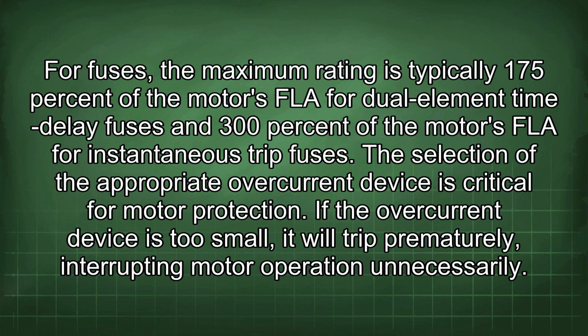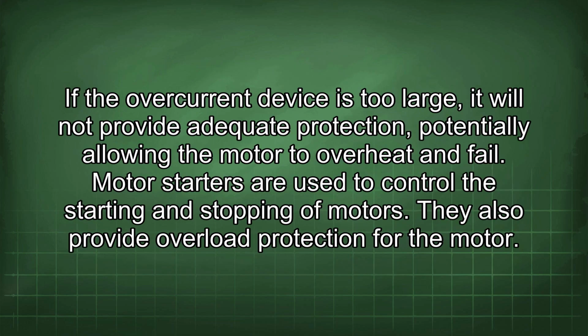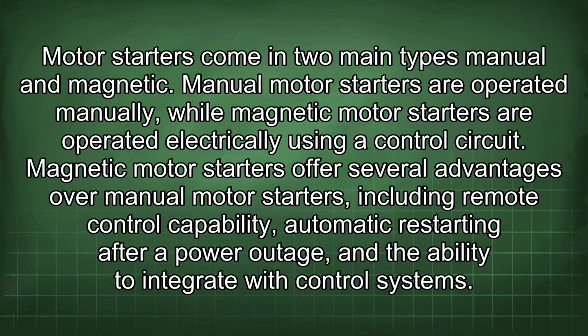The selection of the appropriate overcurrent device is critical for motor protection. If the overcurrent device is too small, it will trip prematurely, interrupting motor operation unnecessarily. If the overcurrent device is too large, it will not provide adequate protection, potentially allowing the motor to overheat and fail. Motor starters are used to control the starting and stopping of motors. They also provide overload protection for the motor. Motor starters come in two main types: manual and magnetic. Manual motor starters are operated manually, while magnetic motor starters are operated electrically using a control circuit.